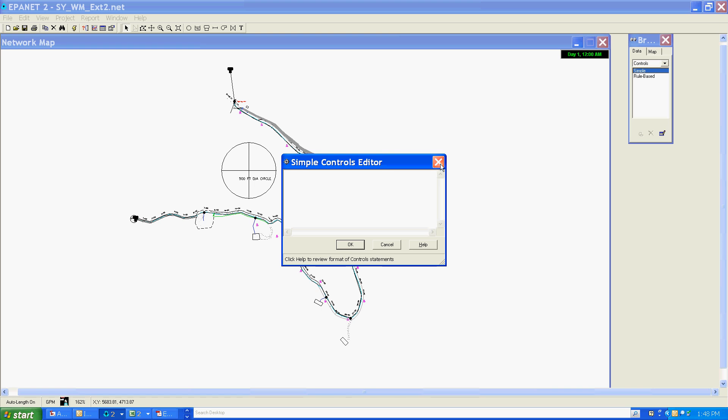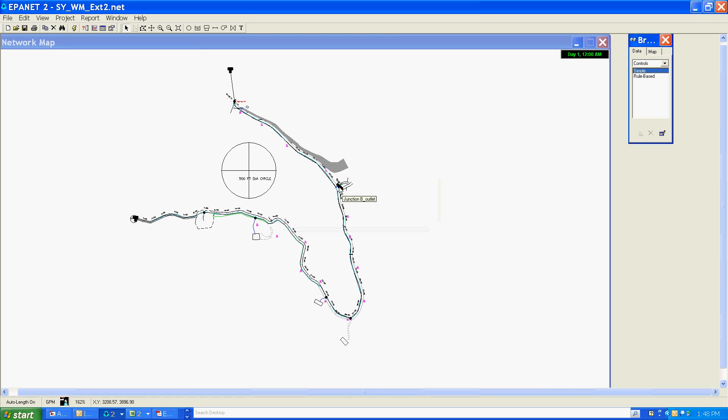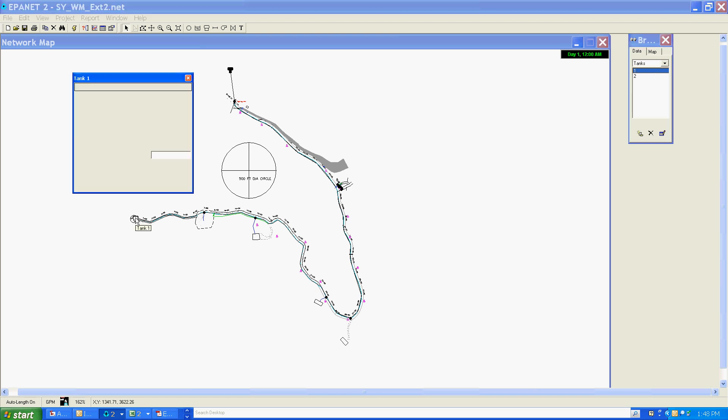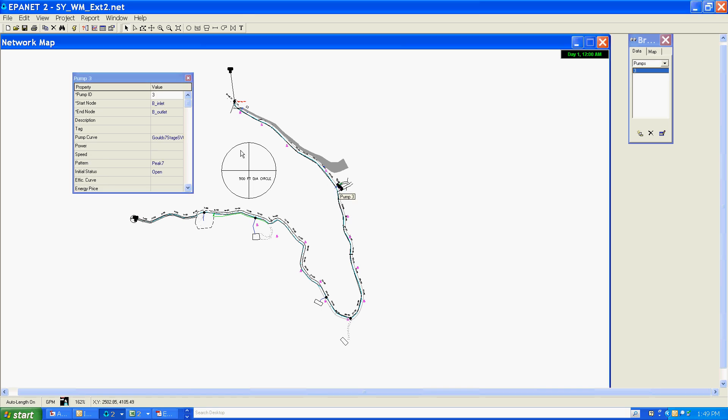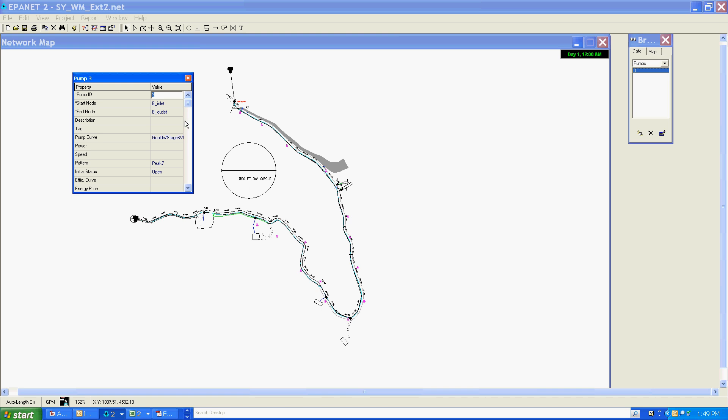First, let me change the names of the pump and the tank of interest. These are the two components of interest. I want this pump to come on whenever this tank is about half full and switch off when it's near the top of its overflow. Remembering that this tank is a 12-foot diameter by 12-foot tall tank, I'm going to want this pump to switch off at about 11.5 feet, when the water level is at 11.5. So I'm going to rename this tank to make it more intuitive when I read my simple controls. I'm going to call it the high tank, and I'm going to rename this pump as B1 for booster 1.